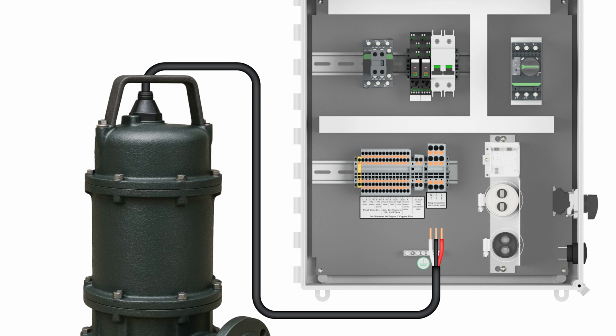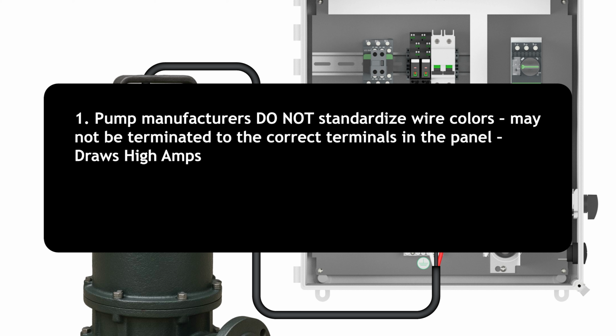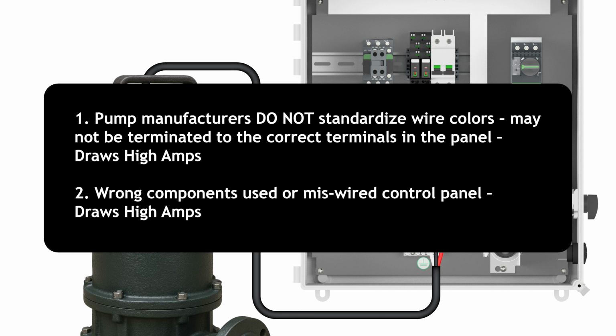Why do we say this? The reason is twofold. 1. The pump manufacturers do not standardize on wire colors for the common, main, and start windings, so they may not be wired to the correct terminals in the panel. 2. Human error in wiring the capacitor kits in the panel or wrong components used.